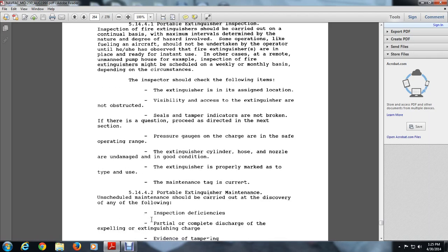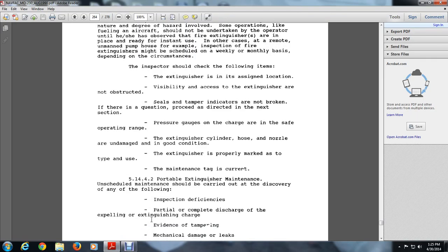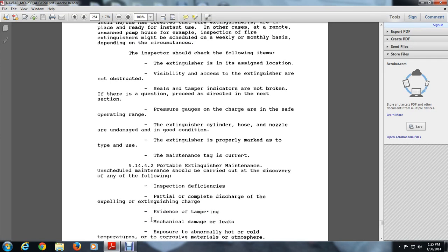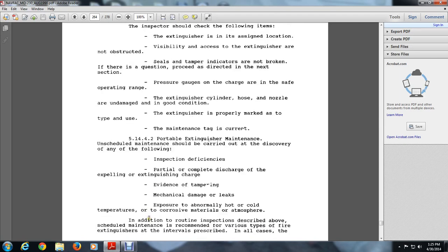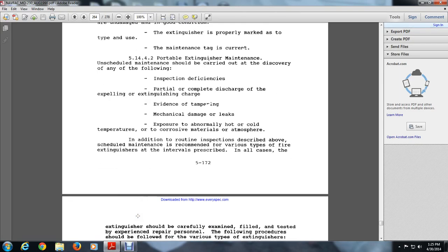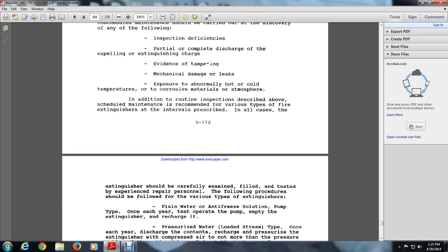514.42, portable extinguisher maintenance. Scheduled maintenance should be carried out for the discovery of any of the following: inspection deficiency, partial or complete discharge, evidence of tampering, mechanical damage or leaks, exposure to abnormally hot or cold temperatures, or corrosive material or atmosphere, and in addition to the routine inspection described above. The scheduled maintenance and recommended intervals for various types of fire extinguishers are prescribed in all cases. Extinguishers should be carefully examined, filled, and tested.